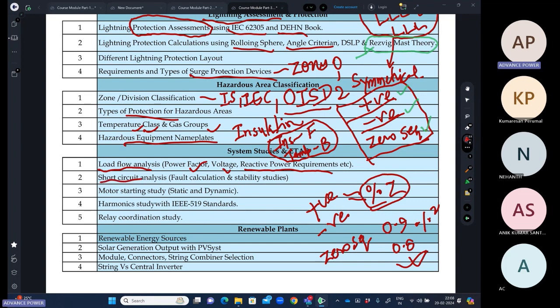Then we'll discuss the short circuit analysis. We'll do the fault calculation. You know the generator is definitely the source which is supplying the fault, but you might have heard also that during fault the motors also supply the fault contribution. It is equal to the starting current of the motor, the amplitude will be that much. When the fault happens, for the starting 2-3 cycles, like for 40 to 60 milliseconds, the residual flux which is there in the motor will contribute to the fault current. So in ETAP also we'll see how much contribution we are getting from the different motors also.